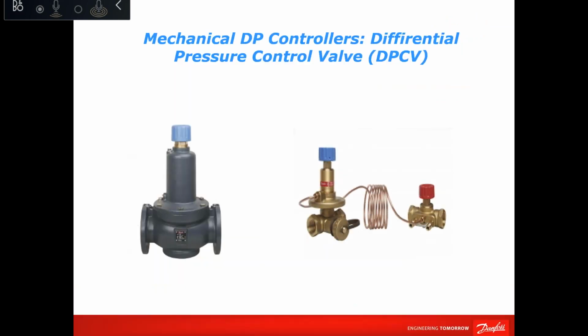So in the next slide, we can see that 35, 40 years back, differential pressure controllers were introduced to the market for the main purpose to control and reduce the effect of system pressure. Because when we reduce the effect of system pressure, we improve the controllability of the valves and we save energy. So for us, the goal is to be able to open the valve at a very small opening in order to first achieve the required comfort level at part load condition, which is 95% of the year. Second, not affecting the overall hydronic balance and control precision.